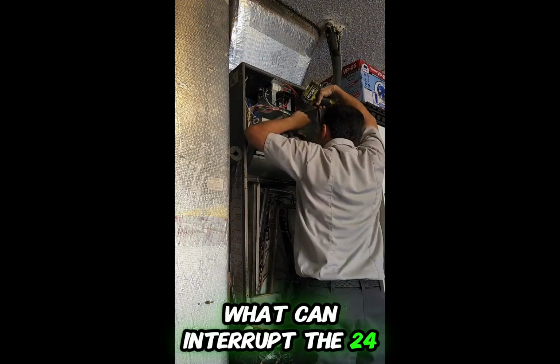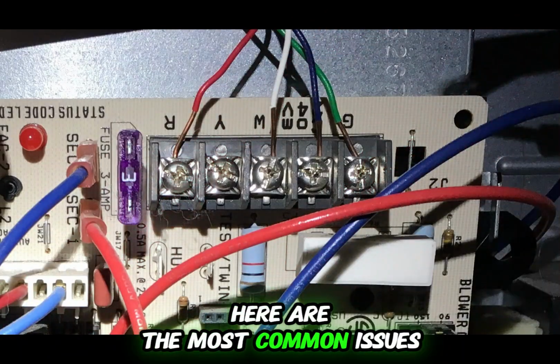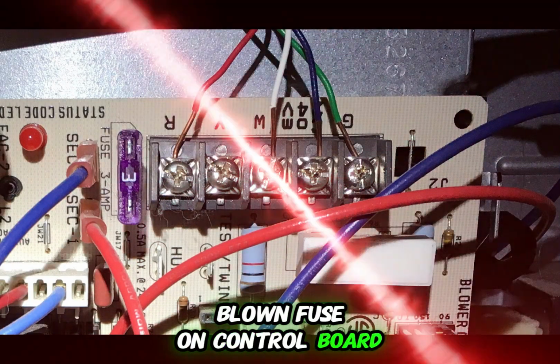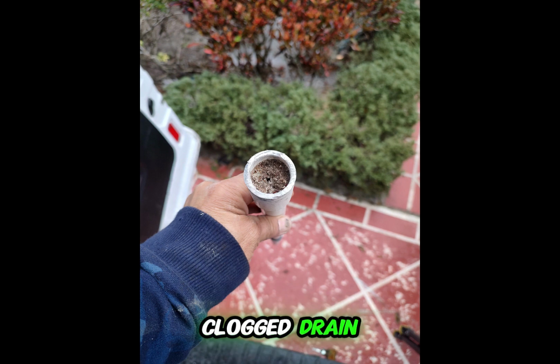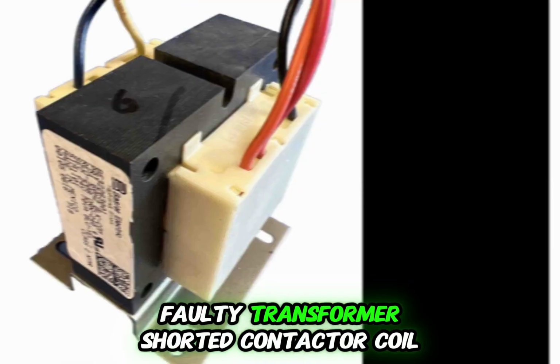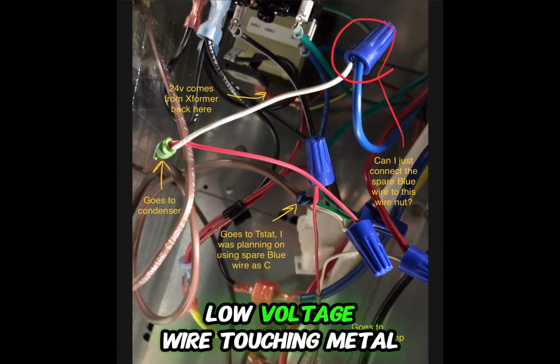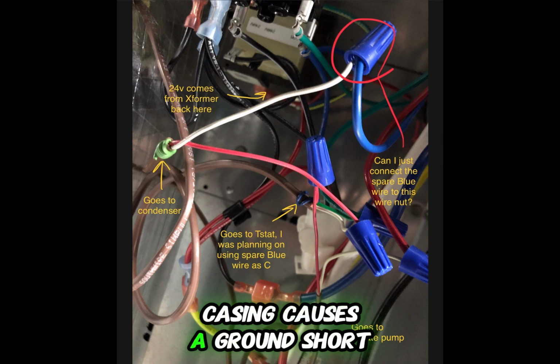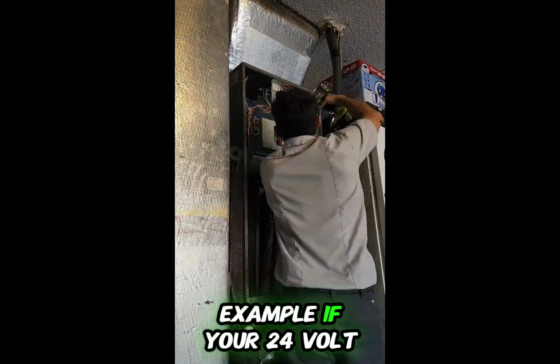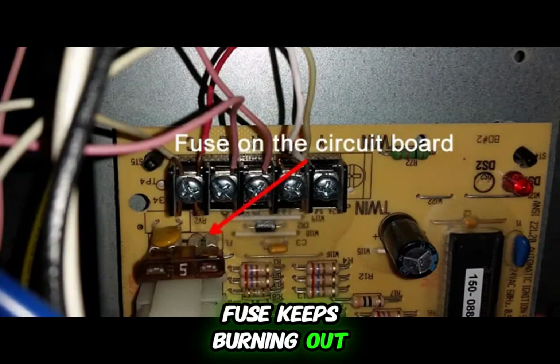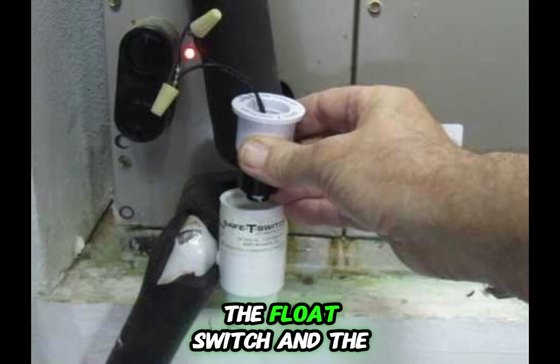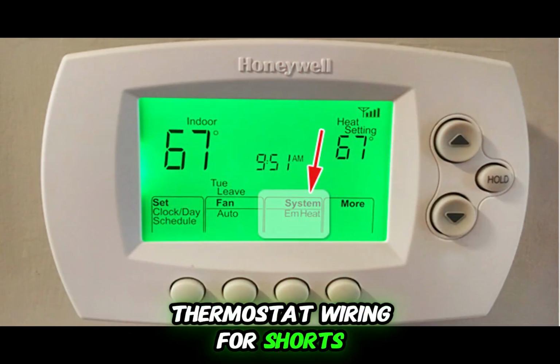What can interrupt the 24-volt circuit? Here are the most common issues: a blown fuse on the control board, a tripped float switch due to a clogged drain, a faulty transformer, a shorted contactor coil, and a low-voltage wire touching the metal casing, which causes a ground short. Example: if your 24-volt fuse keeps burning out, check the contactor, the float switch, and the thermostat wiring for shorts.